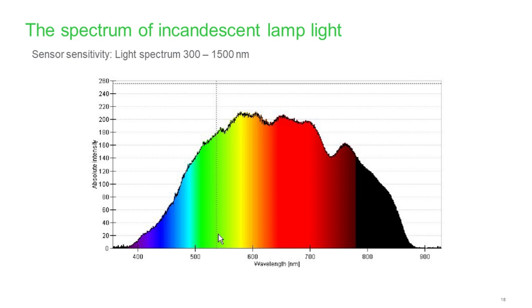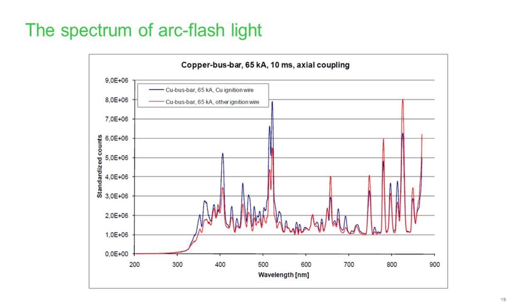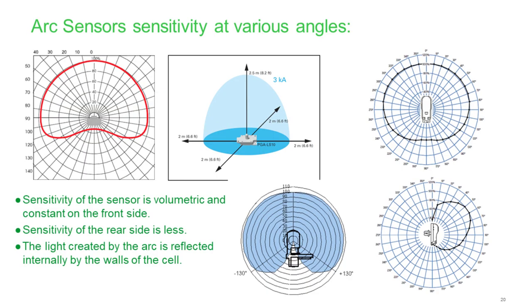Regarding the spectrum of light: visible light from an incandescent source spans 400 to 900 nanometers. Testing on a copper bus bar at 65 kA with a 10 millisecond duration shows a similar wavelength range from 300 to 900 nanometers — all visible light spectrum plus some infrared and ultraviolet. The majority of energy is around the yellow and red light. So our sensor should cover the entire spectrum of light.